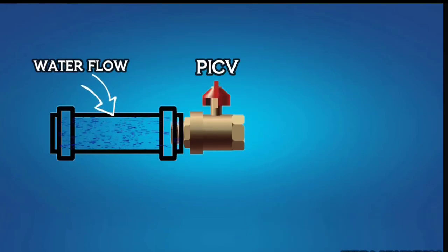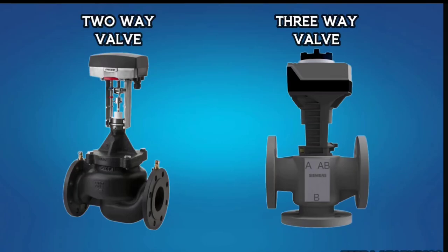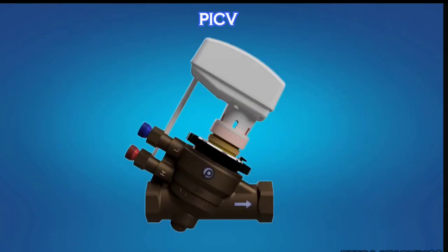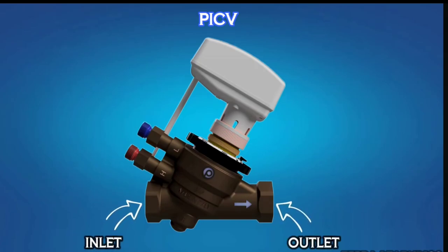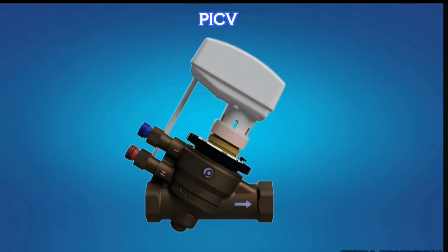It has two valves, namely, two-way valve and three-way valve. In the next video, we will discuss about these two valves clearly. Let's see its important parts. In PICV, it is inlet, and it is outlet. The water comes in through the inlet and goes out through the outlet. This is the measuring port through which the pressure of the water can be measured using a manual measuring meter.